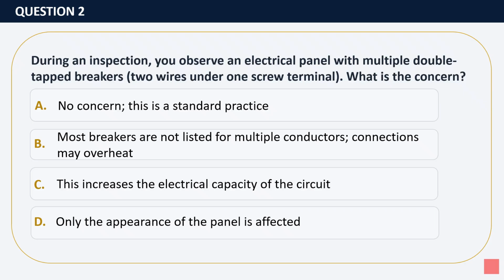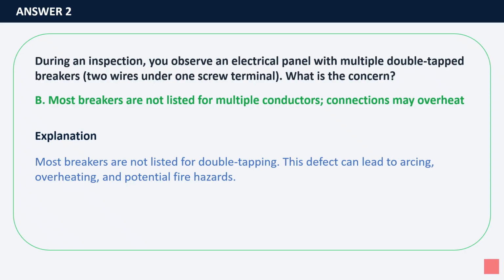Question 2. During an inspection, you observe an electrical panel with multiple double-tapped breakers, 2 wires under one screw terminal. What is the concern? A. No concern. This is a standard practice. B. Most breakers are not listed for multiple conductors. Connections may overheat. C. This increases the electrical capacity of the circuit. D. Only the appearance of the panel is affected. Answer B. Explanation: most breakers are not listed for double tapping. This defect can lead to arcing, overheating, and potential fire hazards.